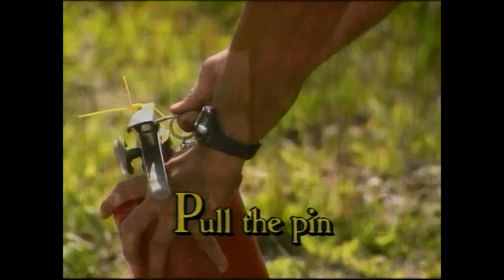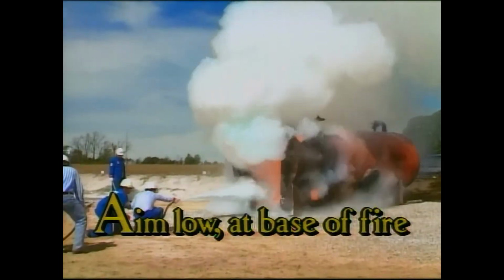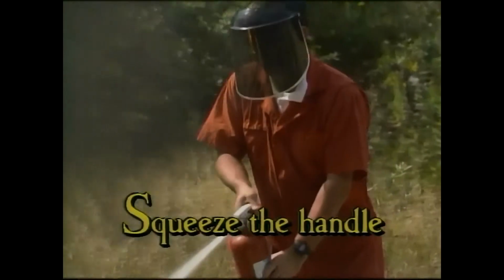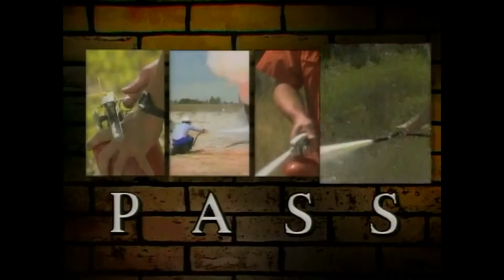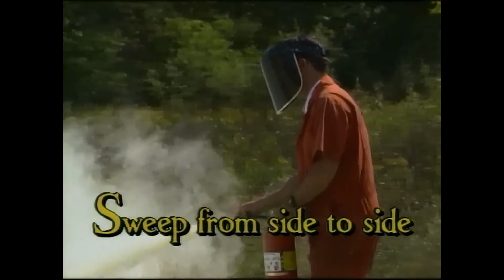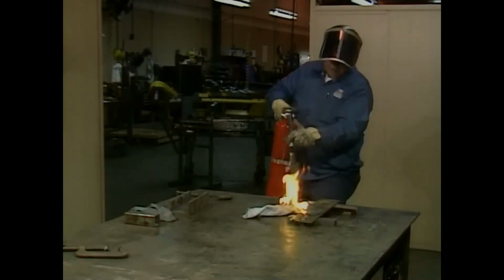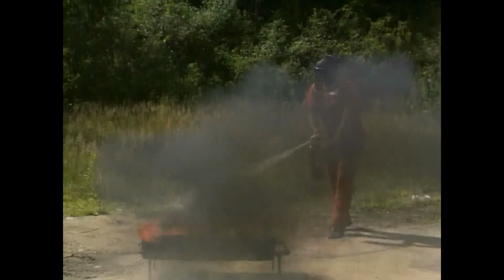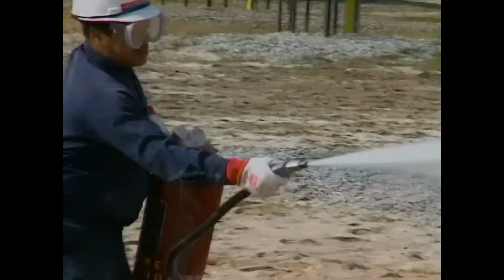When using a fire extinguisher, remember one key word: PASS. Pull the pin. Aim low, point at the base of the fire. Squeeze the handle to release the extinguishing agent, and sweep from side to side to prevent the fire from spreading. Keep your back to an escape route at all times. Know the range of the extinguisher and advance on the fire only as it is being extinguished.